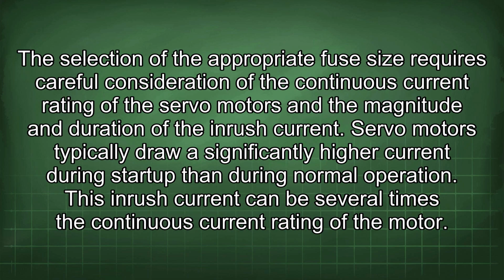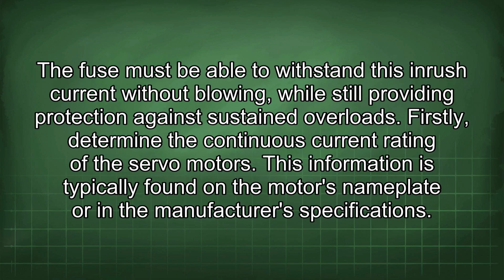The selection of the appropriate fuse size requires careful consideration of the continuous current rating of the servo motors and the magnitude and duration of the inrush current. Servo motors typically draw significantly higher current during startup than during normal operation. This inrush current can be several times the continuous current rating of the motor. The fuse must be able to withstand this inrush current without blowing, while still providing protection against sustained overloads.